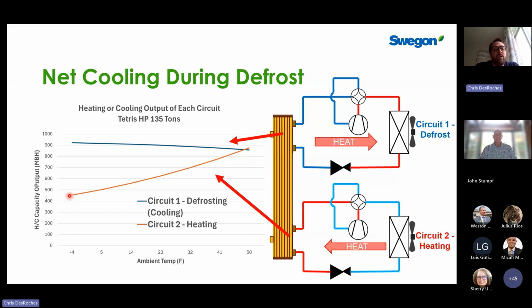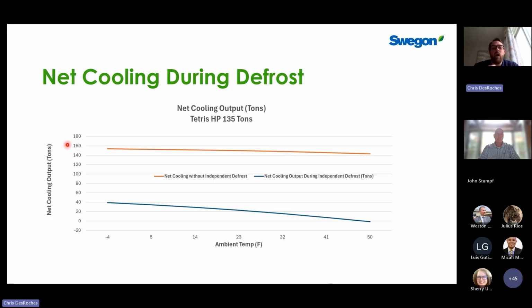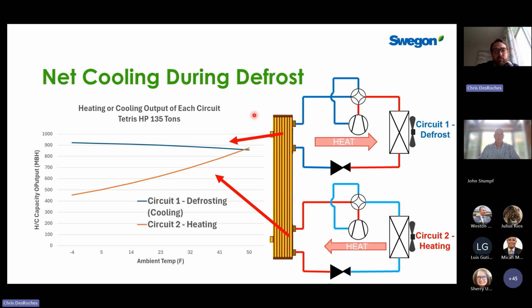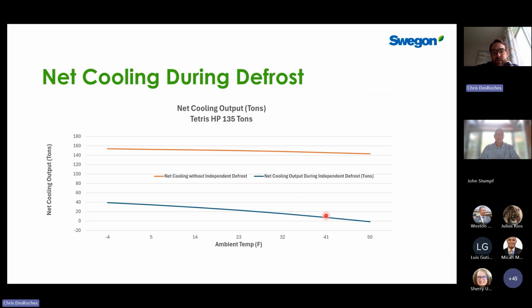So if you look at minus 4F, we have roughly 450 net MBH of cooling that's taking place. This chart here is actually showing the net cooling output. So this bottom example is the sum, whenever you look at whether you're net cooling or heating on this chart, this is the difference between the two. So they're canceling out right at 50 Fahrenheit. As it gets colder, we get more and more net cooling.